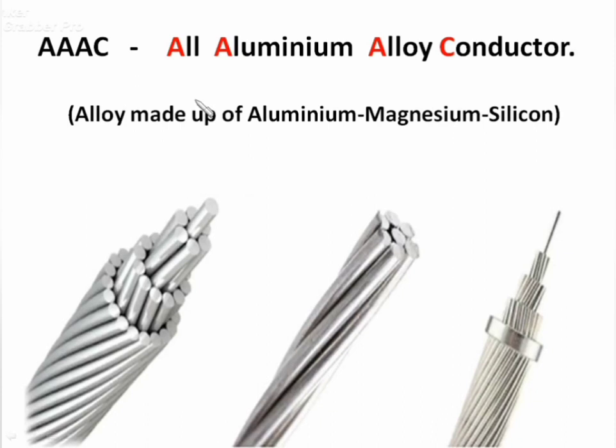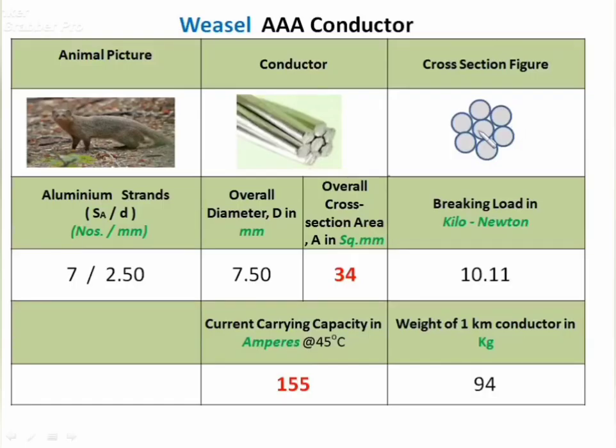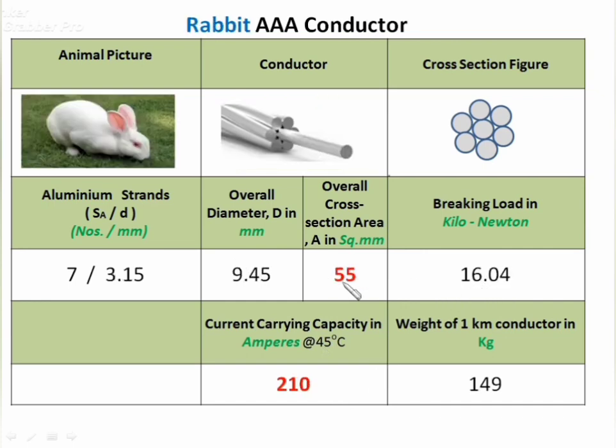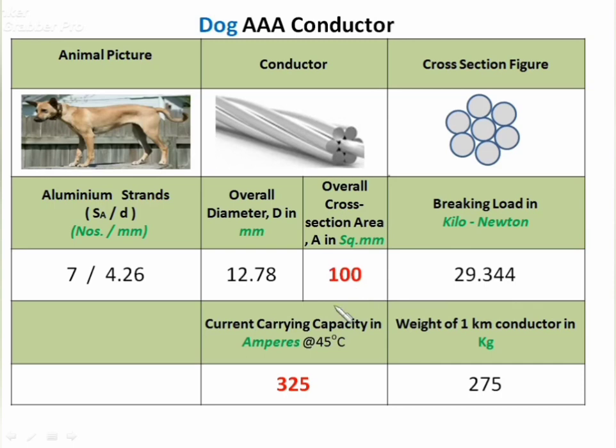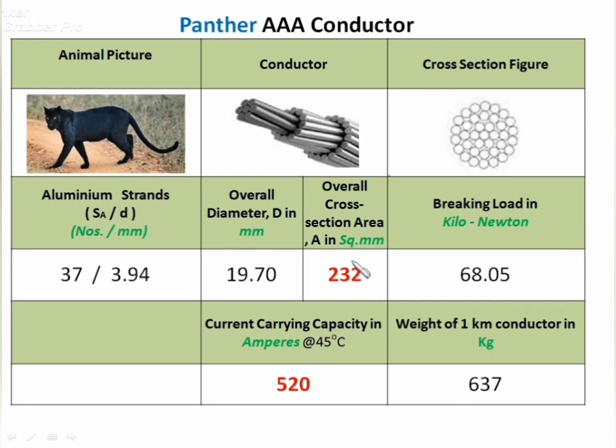Now we will see the AAAC (All Aluminium Alloy Conductor). This alloy is magnesium and silicon mixed with aluminium. Weasel AAAC has cross-sectional area 34 mm² and 155 A current capacity. Rabbit AAAC has 55 mm² area and 210 A current capacity. Dog AAAC has 100 mm² area and 325 A current capacity. Panther AAAC has 232 mm² area and 520 A current capacity.